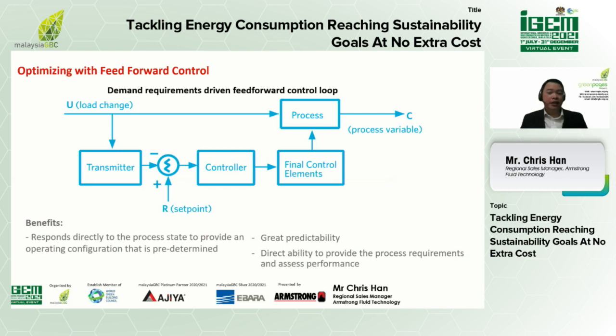For example, a week later, while operating at that same system load with the same settings for all the devices on the control curve, you realize the system is now performing differently. We know something has changed, and we can look into the system and subsystems to diagnose what has deviated from expected performance. This gives us a baseline to work forward from, to see how much we are deviating. In that sense, we can arrest consequential changes early on with quick decision-making and take the necessary corrective actions, helping maintain the system's performance and the building's efficiency levels as desired.